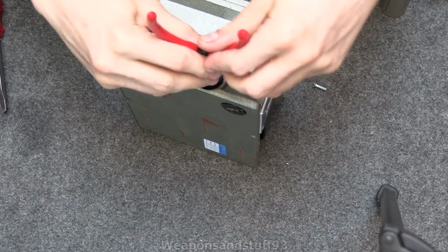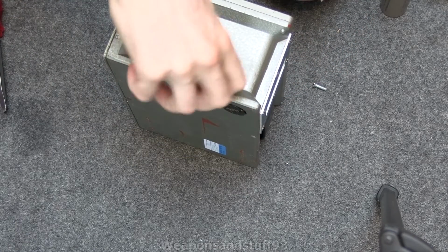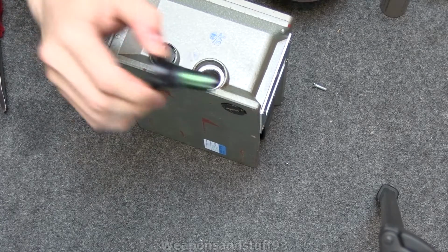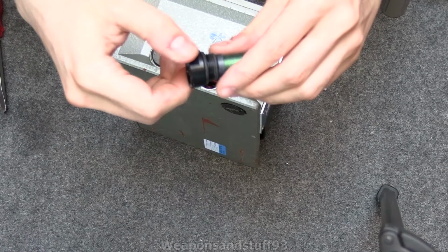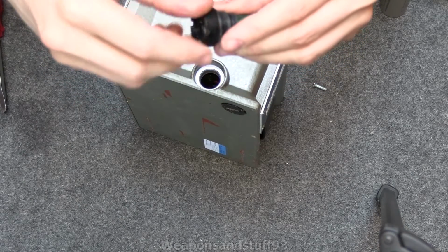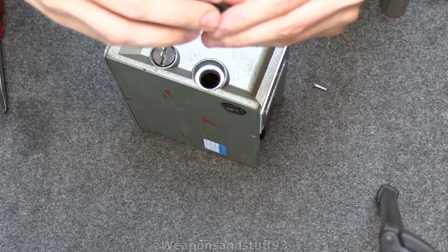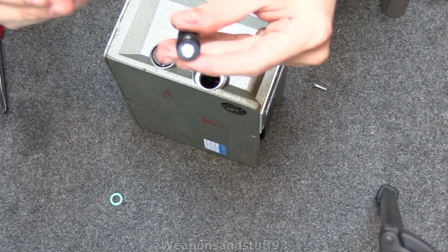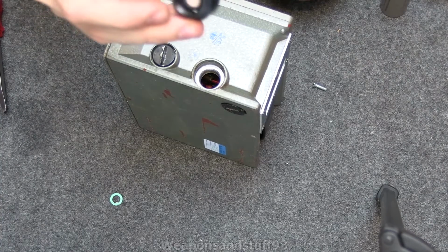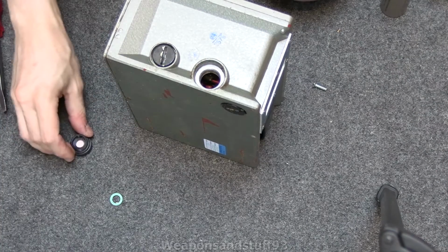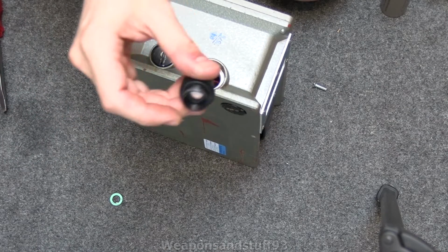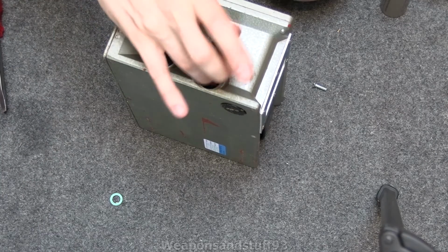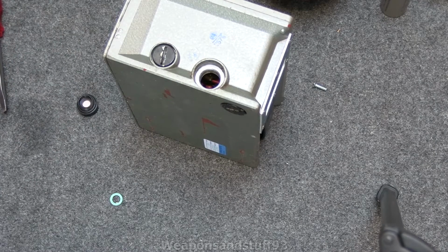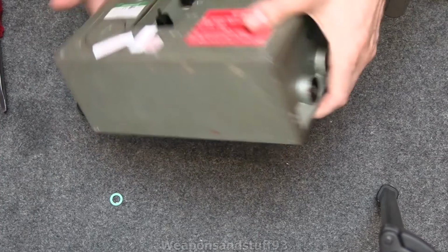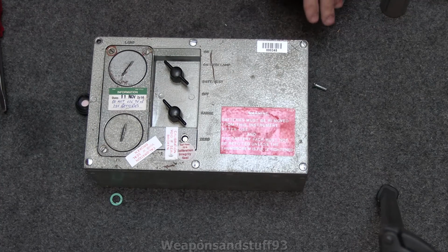So, there we go. Right, it's out. So this is the long since dried up bit of silica gel. What we're going to do using this is twist this bit here, and what you'll see happen is the old silica gel, which is pretty much rock solid in there, looks like that. So what we've got now is this bit ready like that. Put this to the side, we're going to need it later. And what we're going to do is put some fresh silica gel in that area of the ion chamber, but it's easier to do that from the inside, not the outside, so I'll show you that in a second. What I'm going to do now is stop the video so it doesn't go into 2 really long segments, so it's 2 segments, not 1 really long segment.